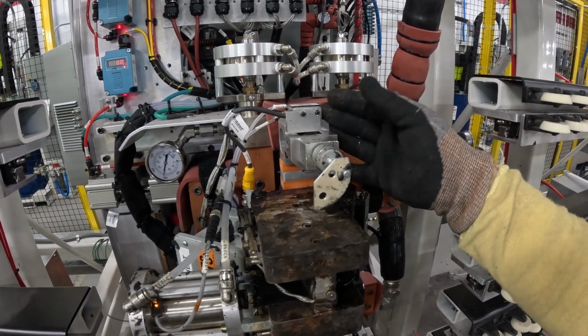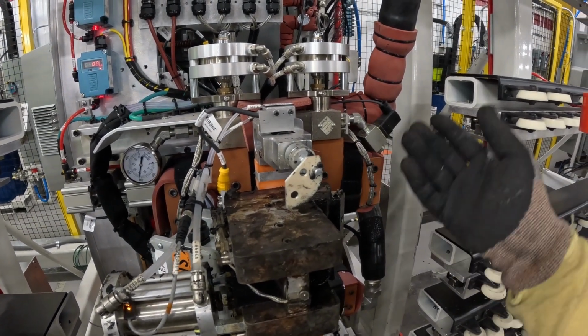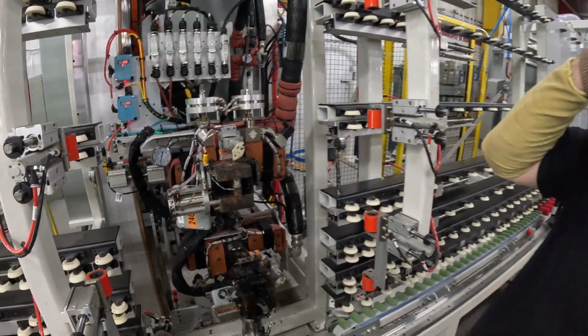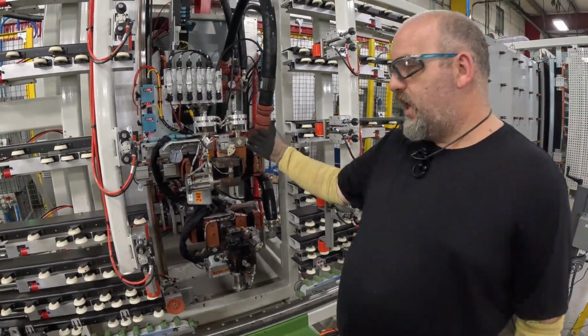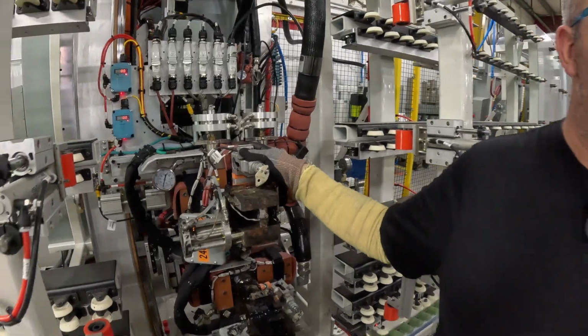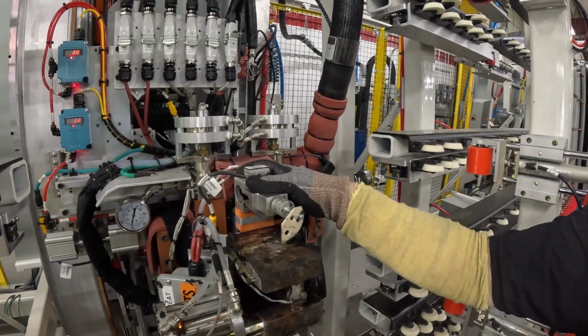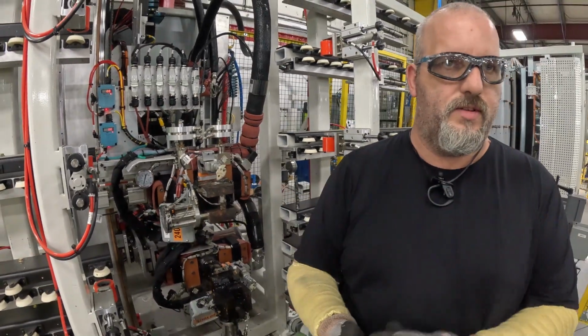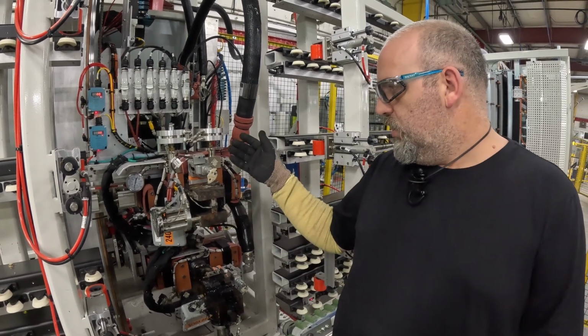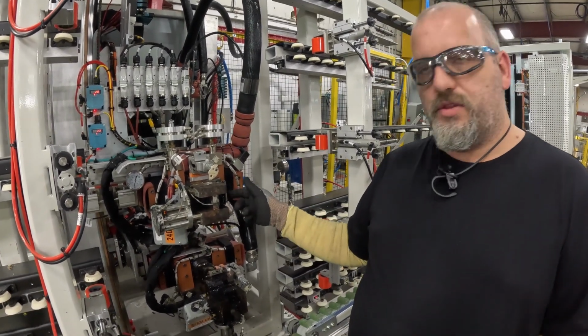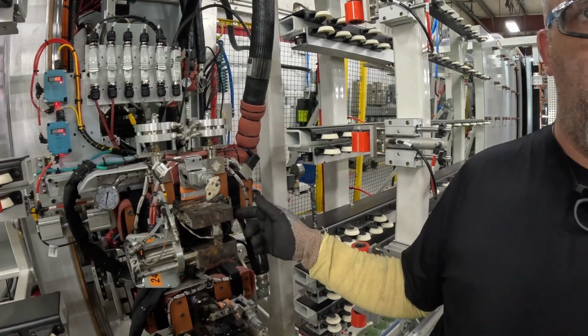If this is loose, fix it and recalibrate. Reminder: if you take this off because it's loose, or if it becomes loose and you have to retighten it, or you take it off to service it for whatever reason, you're going to have to go through and calibrate your depth probes on all your nozzles.